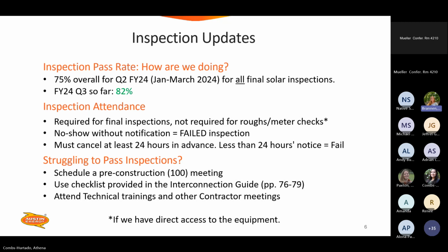That said, a couple of things as a reminder of what goes into these. Inspection attendance is really important. Obviously, when you need to be there for a final, you are required to be there. It is not required for roughs or meter checks. So you don't have to be there as long as we have access to the equipment. If we don't have access to the equipment, you do still need to be there for a rough or a meter check. No shows without notifications is a failed inspection. Please cancel at least 24 hours in advance. That'll help us keep you from failing that inspection. If it's less than 24 hours notice, it's more likely than not going to be a fail.